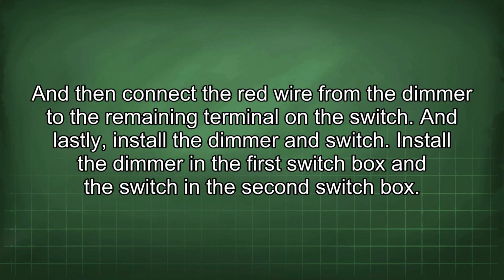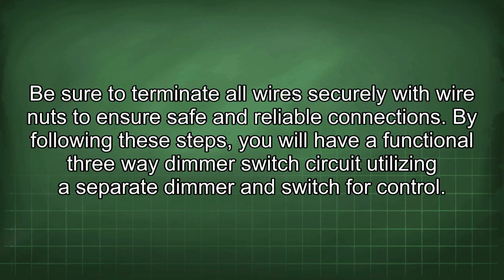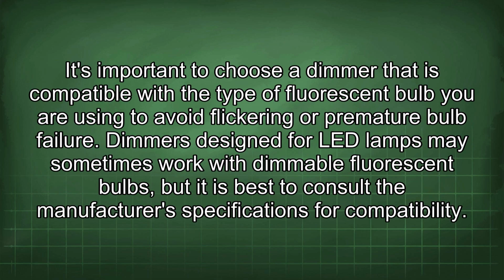And lastly, install the dimmer and switch. Install the dimmer in the first switch box and the switch in the second switch box. Be sure to terminate all wires securely with wire nuts to ensure safe and reliable connections. By following these steps, you will have a functional three-way dimmer switch circuit utilizing a separate dimmer and switch for control. It's important to choose a dimmer that is compatible with the type of fluorescent bulb you are using to avoid flickering or premature bulb failure.